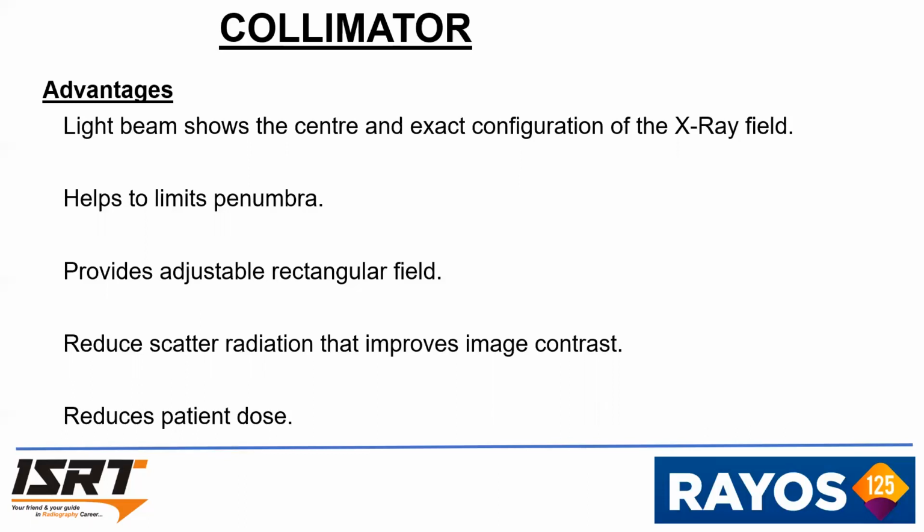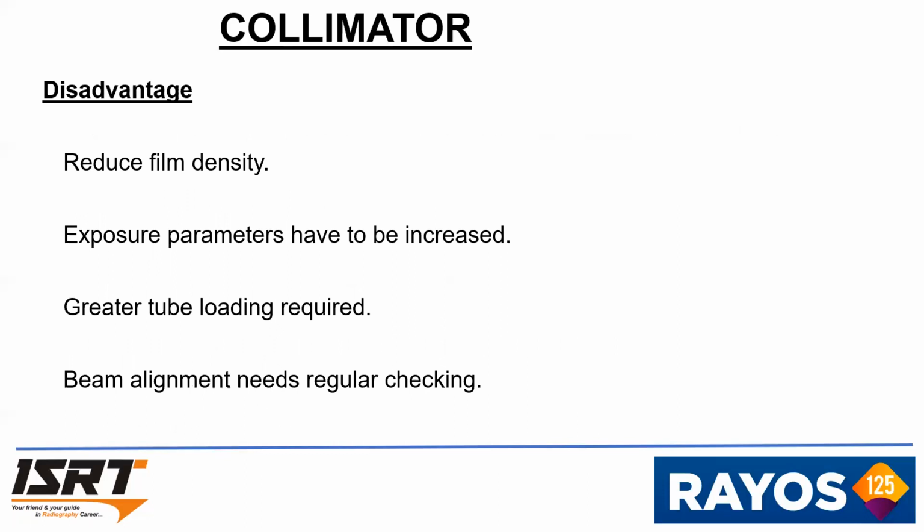Compared with the other two beam restricting devices that we discussed, it provides adjustable fields, rectangular or square, whatever field we need, provided by the collimator. It reduces scatter radiation and improves image contrast. And definitely it will reduce the patient dose also.